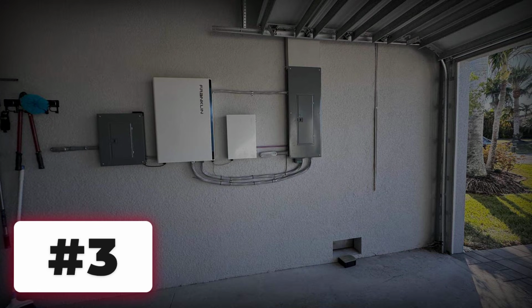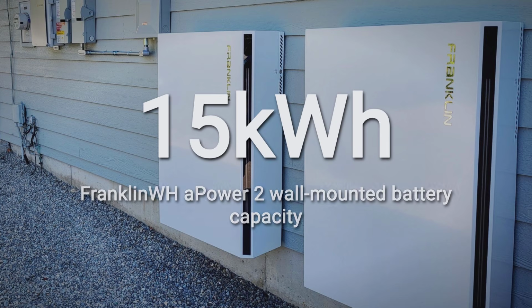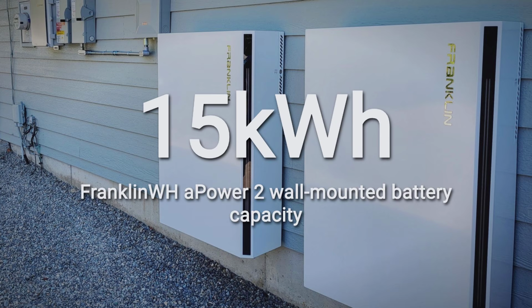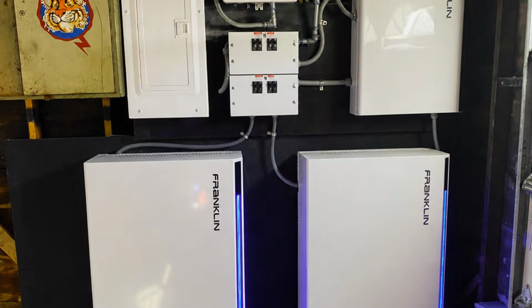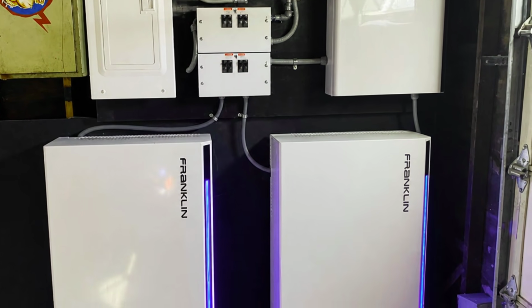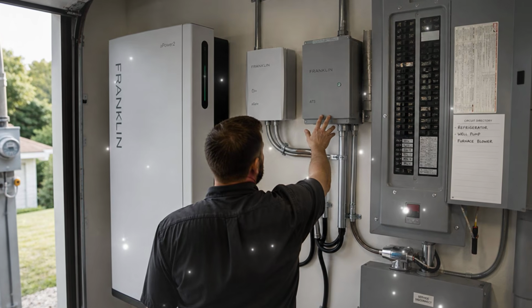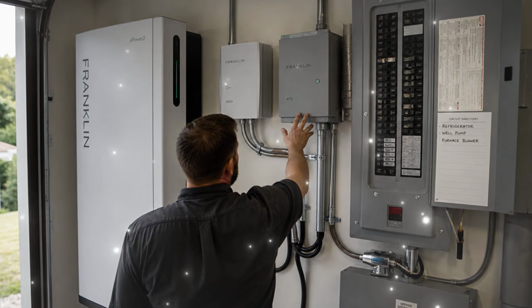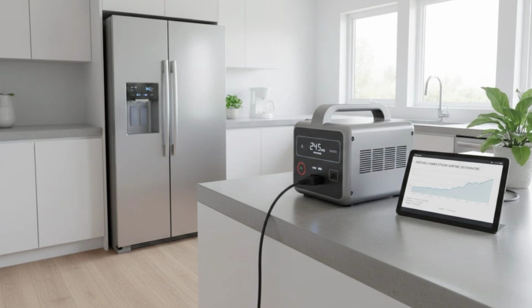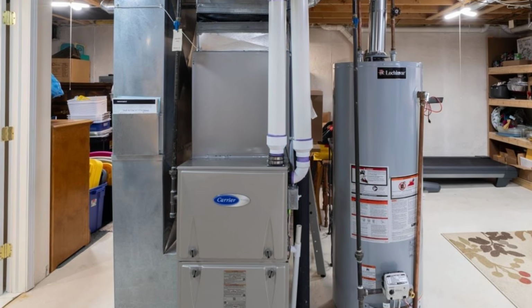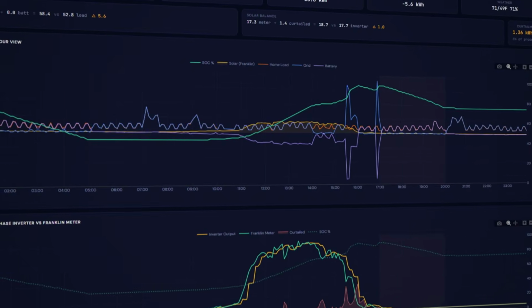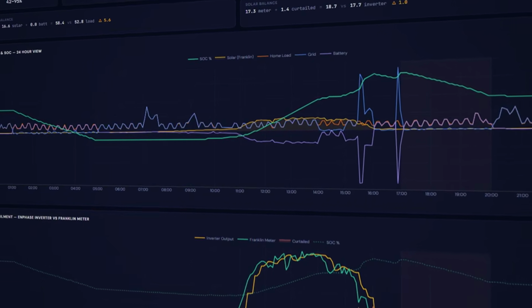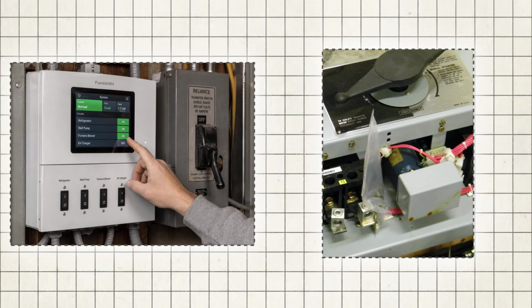Number 3, and this is the one I'd put in my own house, is the FranklinWH aPower 2, a 15 kilowatt-hour wall-mounted unit paired with a separate controller called the A-Gate, usually mounted right next to the main electrical panel in the garage. This is the closest thing to a true whole-home system on this entire list. It puts out 10 kilowatts continuously, enough for the fridge, the well pump, the furnace blower, and the lights all running at the same time. And the A-Gate controller gives you circuit-by-circuit control instead of an all-or-nothing backup.